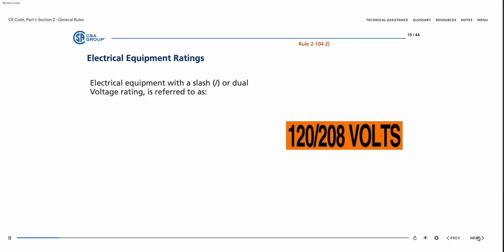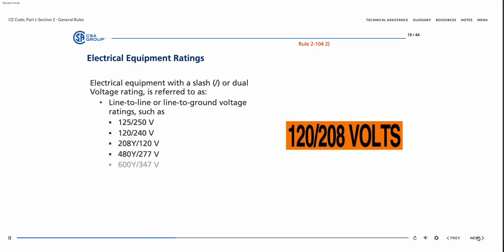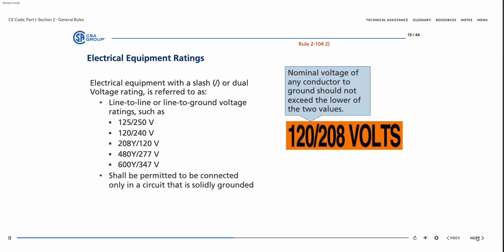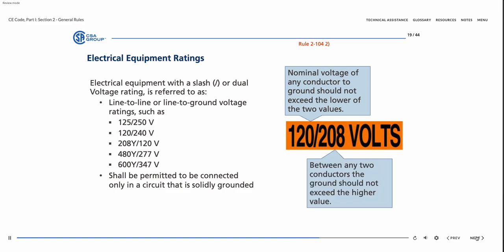Electrical equipment with a slash, which indicates a dual voltage rating, is referred to as line-to-line or line-to-ground voltage rating and is to be connected only in a circuit that is solidly grounded. Nominal voltage of any conductor to ground should not exceed the lower of the two values of the equipment voltage rating. Between any two conductors, the voltage should not exceed the higher value of the electrical equipment's voltage rating.